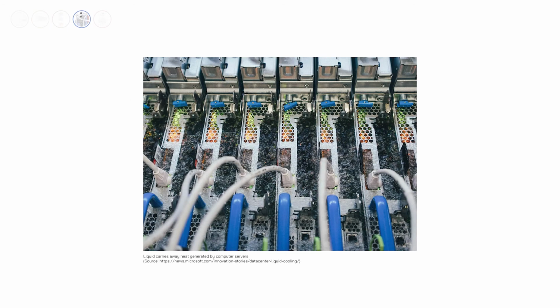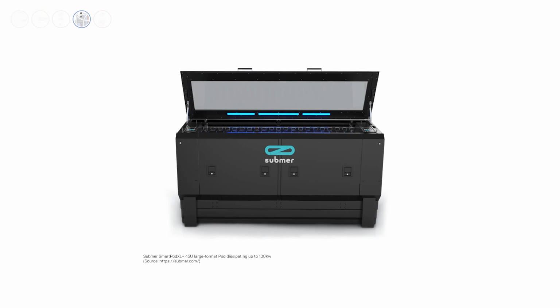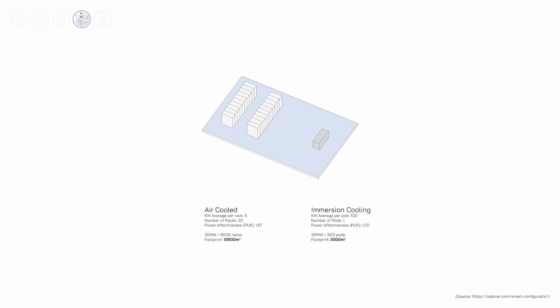The data center utilizes an immersive cooling strategy to reduce the overall footprint of equipment required when compared to a traditional data center arrangement. A traditional server arrangement would require 6,000 5-kilowatt racks to achieve a 30-megawatt data center. With the high-density arrangement possible with immersive cooling, this would be reduced to 300 immersive cooling modules.